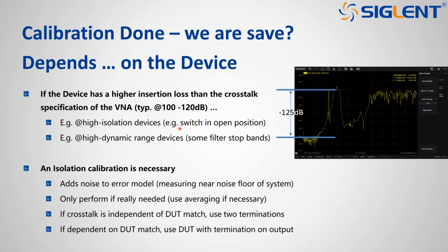Or you have very high dynamic range devices, like the filter we have here on the right side, which has a 125 dB stop band, and this then already comes into the critical measurement region. To solve this, there is a possibility of doing a specialized isolation calibration. Of course, everything good also brings something bad. In this case, we are working very close to the noise level of the analyzer. Of course, this also has to be considered in the measurements and in the complete error model. We have to use a lot of averaging to smooth everything out and get clean results, to be able to do this isolation calibration properly.